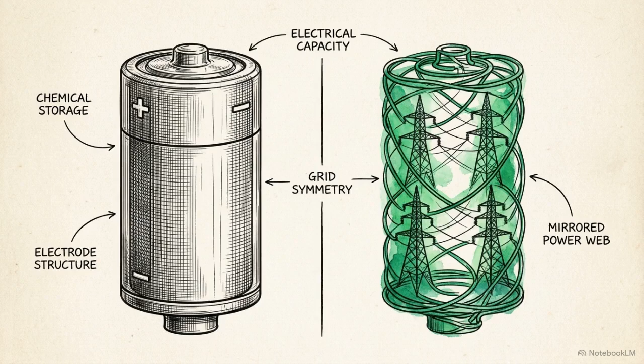Bangladesh connects to India through the 400 kilovolt Baharampur-Bheramara line, supported by specialized 500 megawatt high-voltage direct current terminals that safely bridge the two national systems. Right now, those cables are actively pulling in 1,160 megawatts of electricity from India and another 40 megawatts of hydropower routed directly from Nepal. By moving surplus power from where it's generated to where it's needed across large geographical distances, this hardware network acts as a giant virtual battery.